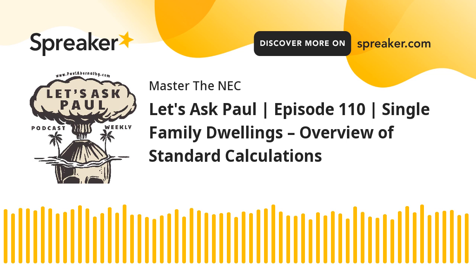Also, if you read 220.14J, you'll see that there's a 1, a 2, and a 3. The general lighting that's in this dwelling is also covered by that 3 VA per square foot. It's already in there. So your general use receptacles are in there. Your general lighting outlets are in there. All that general stuff is already part of that 3 VA per square foot. Don't have to do anything extra. All right, so you would write that down typically.